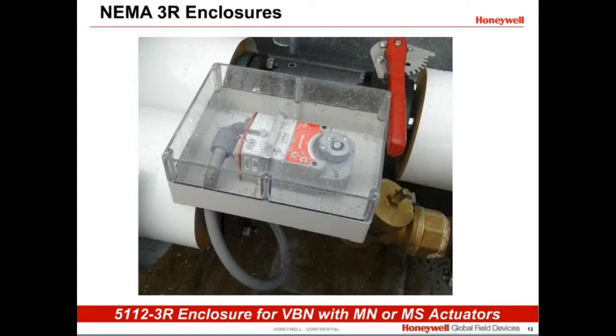For applications where the actuator is exposed to outdoor elements, a rainproof actuator enclosure with see-through covers is available for direct couple actuators like the MN6105 or MN7105. This enclosure is rated to NEMA 3R. This rating is equivalent to an IP14 ingress protection rating. It will protect the actuator from dirt, rain, sleet, snow, and ice. The part number is 5112-3R.